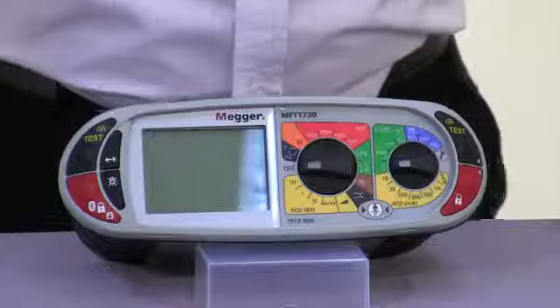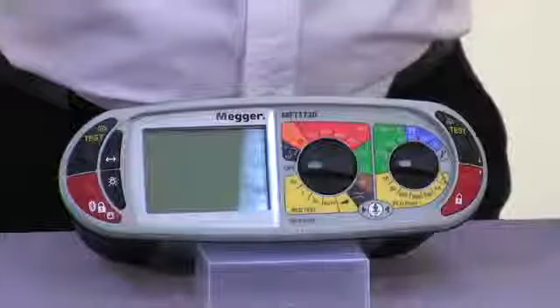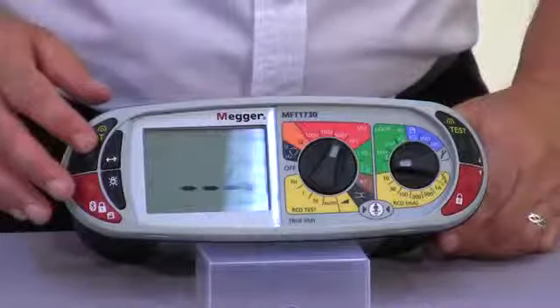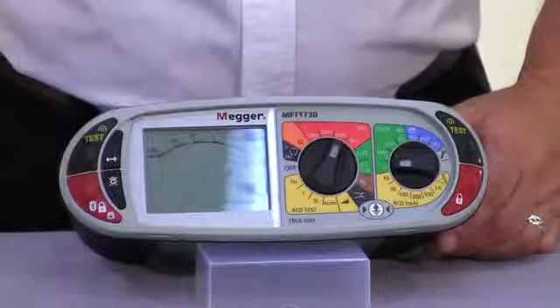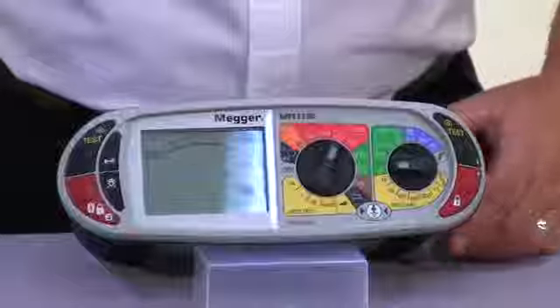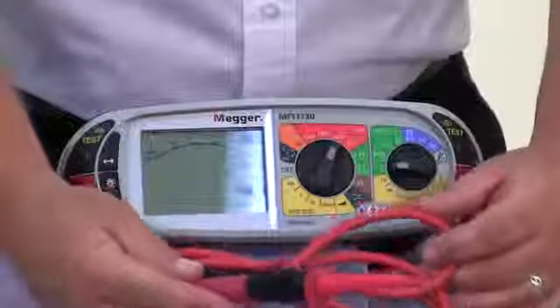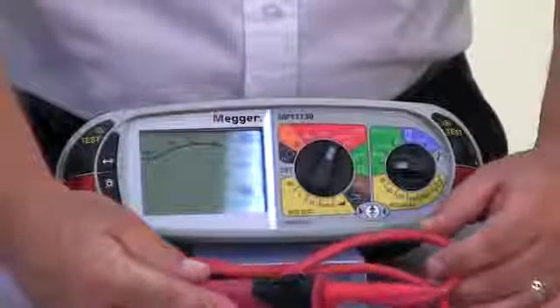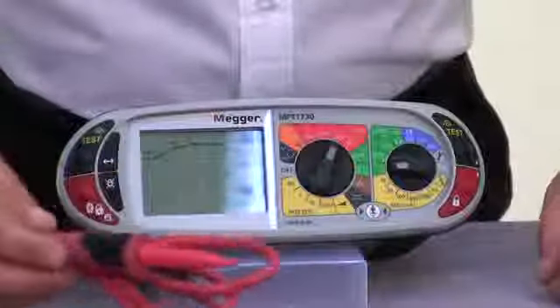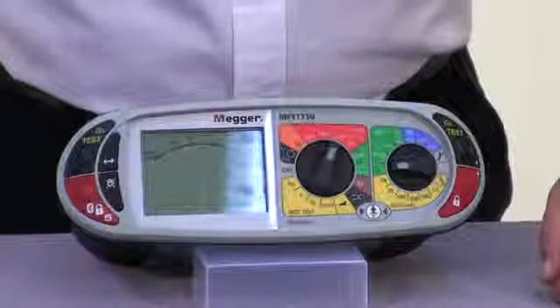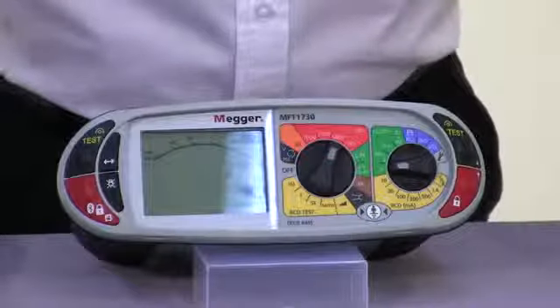Insulation testing on the MFT1700 series is just a case of dialing up our desired test voltage and pressing our test button. One of the things that you get with the 1720 and the 1730 models is the remote switch probe. This just allows you to maintain a 2-handed operation, and that is available as an accessory with the MFT1710.